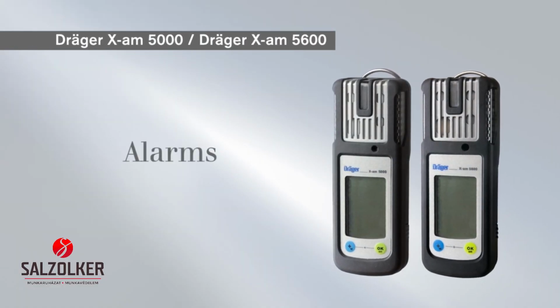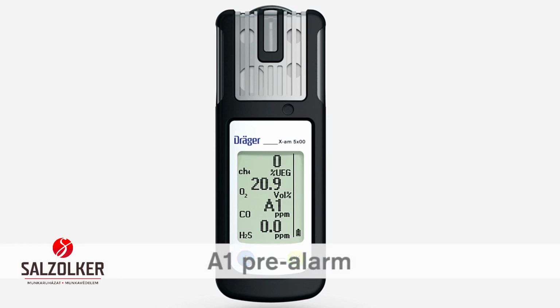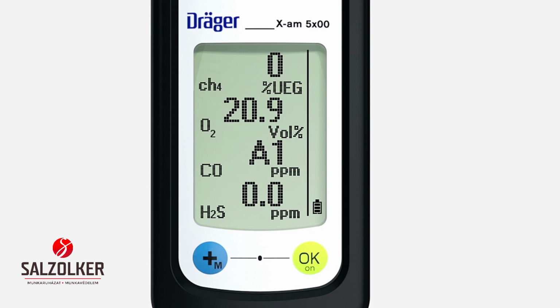We'll start with the A1 pre-warning threshold. The alarm threshold can be changed by using the CC Vision computer software, which is available free of charge on the product page of the X-am 5000 on the Dräger homepage www.dräger.com. The A1 alarm sounds if the concentration is higher than normal but doesn't yet constitute an acute hazard. The audible, visual and vibration alarms are all activated periodically. A1 alternates in the display with the gas concentration. An A1 alarm can be acknowledged by pressing the OK key. The alarm automatically stops as soon as the concentration drops below the defined threshold.